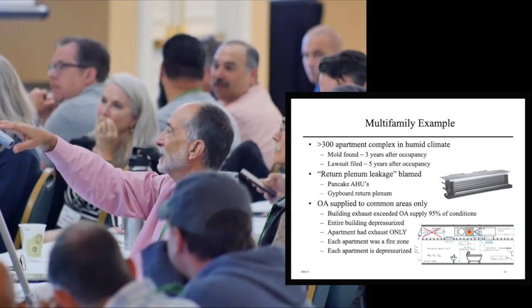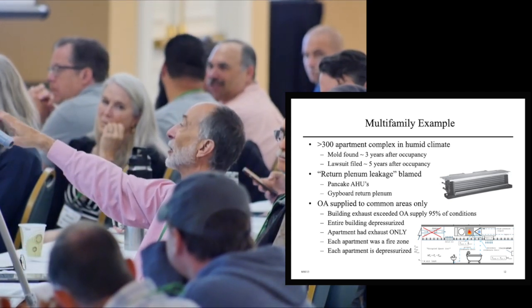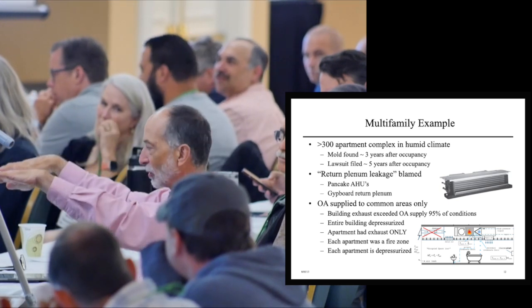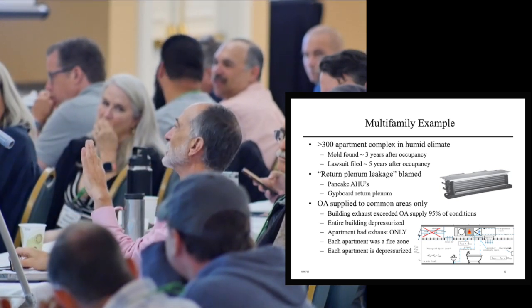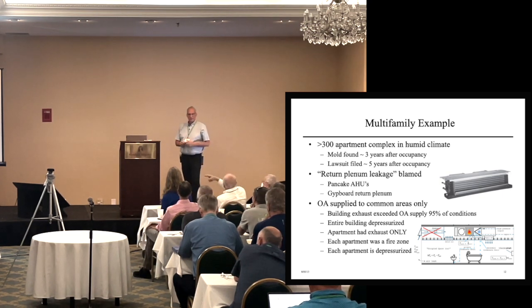And I'm not saying that something that's got 3,000 exhaust excess isn't going to be depressurized. You're totally right. But you can't pressurize something without knowing the enclosure type. Apparently, the buildings you're working on don't leak air. Apparently not. The enclosures apparently have no leakage.